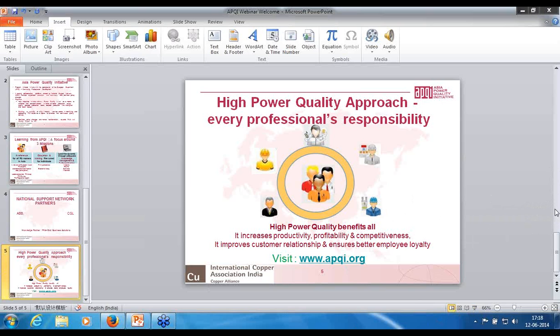So basically, if I have to improve the percentage of T&D loss by means of power quality, I have to improve the Q, that is less Q, and improve the THD, that is less THD. By this, a good percentage of T&D loss can be reduced. As I told, from 30 plus, today we are nearby 20, we have done nothing more than adding this power quality. Now we are planning to add unmanned and all sorts of things, and theft measures, where we are planning to bring it to 15% and further to 12%. So it gives a good amount of savings.